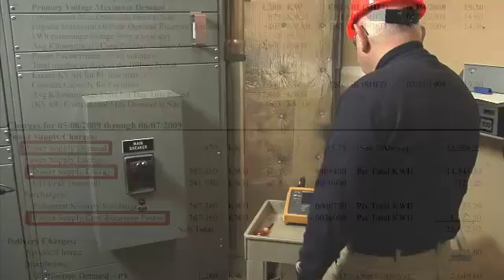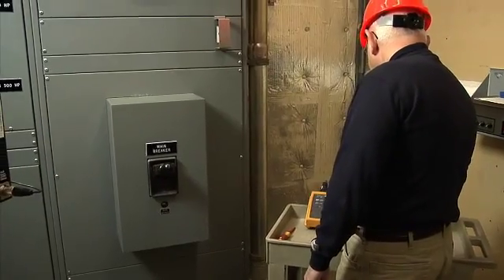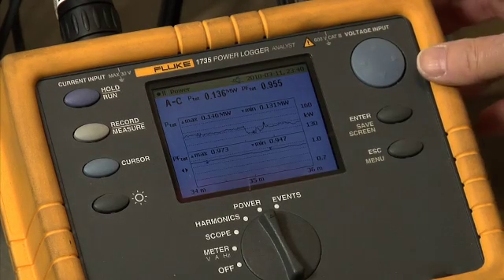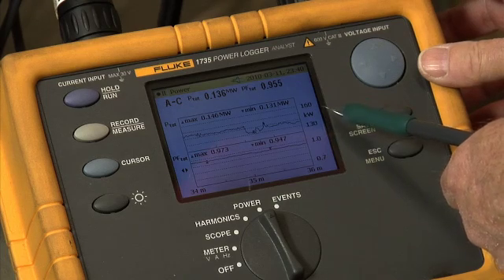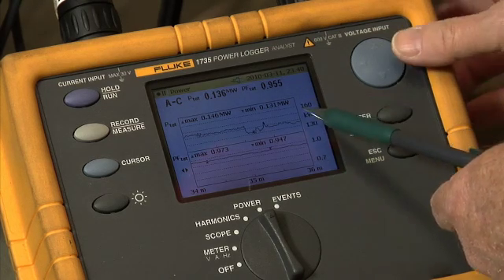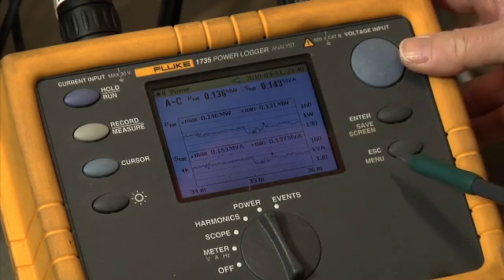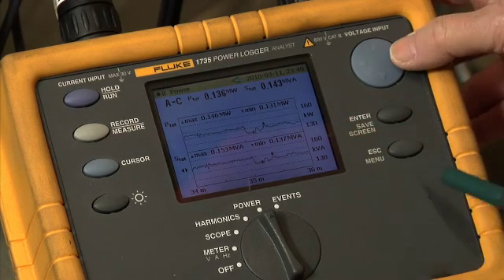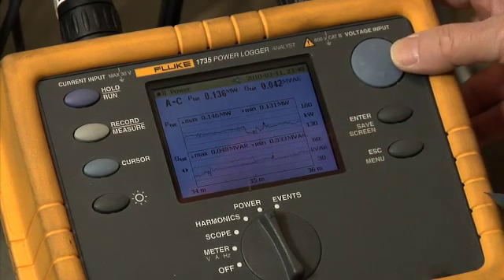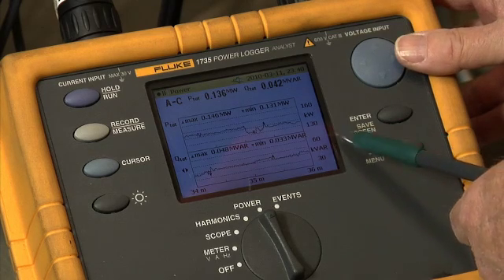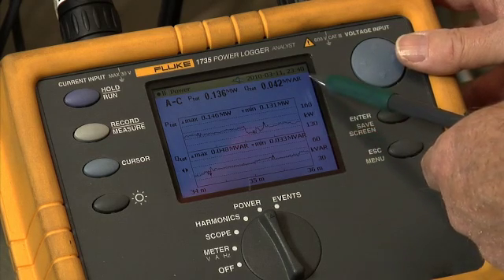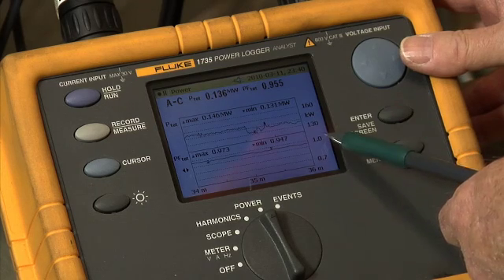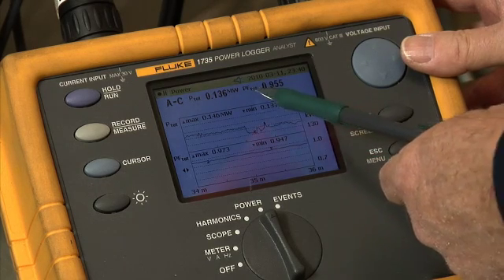As you can see, the Fluke 1735 power logger collects the same data that you saw on your power bill. The top half of the power logger screen shows demand or KW. The next screen shows kilovolt amps or KVA on the bottom, and the corresponding KVA value is shown at the top. The next screen shows the kilovolt amps reactive or KVARs. And on the next screen, power factor is shown — the key parameter we are trying to maintain.